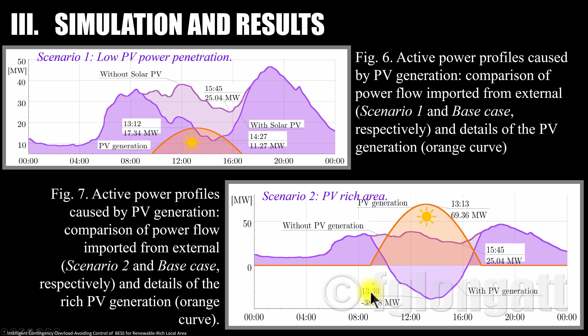You can see that it is reaching around 17 megawatts around 1 p.m. However, if we increase the penetration, I mean the power plant that is installed over there is huge, you can see here how the power production during the sunlight hours is overcoming and reaching almost 70 megawatts at 1 p.m. But now, what is important that you realize for scenario 1, low penetration of PV, and scenario 2, rich PV area, what you can notice is that here we have the classical duck curve. You can see here how during the sunlight hour, the apparent load from the transmission system is reduced. In fact, scenario number 2 is quite interesting because there is a reverse on the power flow on the transmission line.